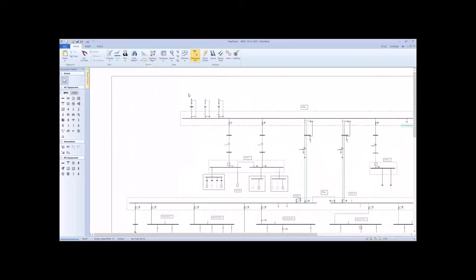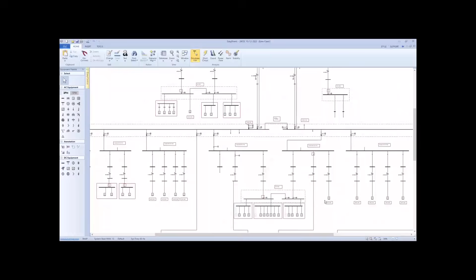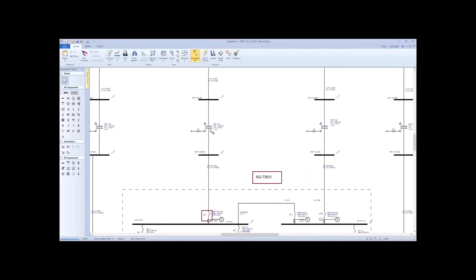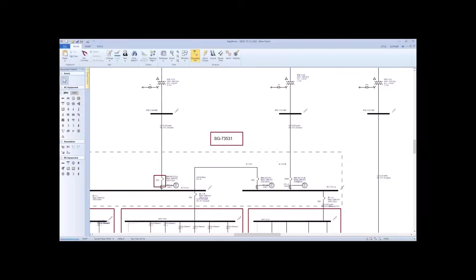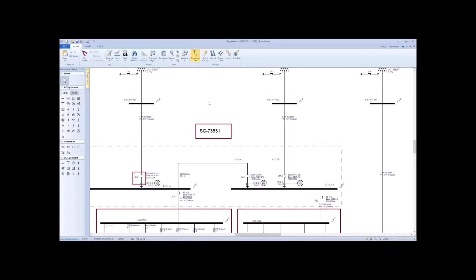Something else which I think is useful: this tool. I come back to base case. Remember, we work on the base case, and if I have other scenarios, I create those scenarios, and on each of those scenarios I make the specific changes, usually opening or closing breakers, something like that. In this project, everything is redundant. We have tie breakers, we have switch gears or MCCs, bus A, bus B, and each of these two buses is connected by a tie breaker, and each power transformer is capable of feeding 100% of the loads downstream. So usually in our model, one incomer is open and the tie breaker is closed. This is the philosophy we are modeling.